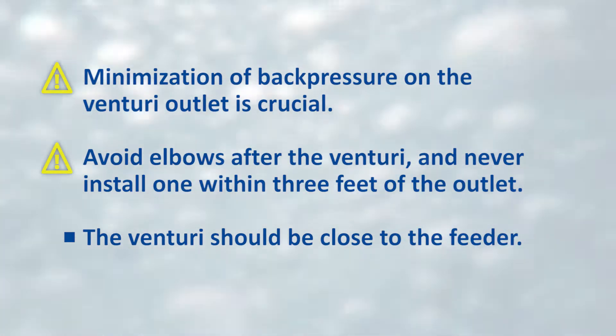Minimization of back pressure on the venturi outlet is crucial for optimal performance. Avoid the use of elbows after the venturi if possible and never install an elbow within 3 feet of the venturi outlet.